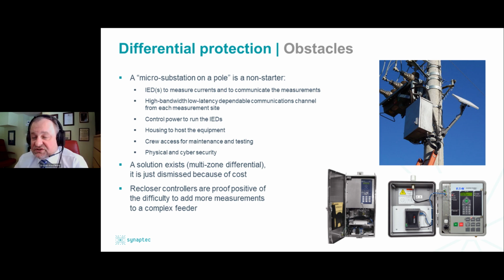So if this is so simple, why aren't we using this? Well, we kind of self-censor ourselves. A micro substation on a pole is a non-starter. If I were to put IEDs to measure the current, then I will have to put a dependable communications channel to communicate those currents. And I would argue that wireless is not going to work for protection applications such as differential. I will need control power to run those IEDs, both relays and the communications gear.